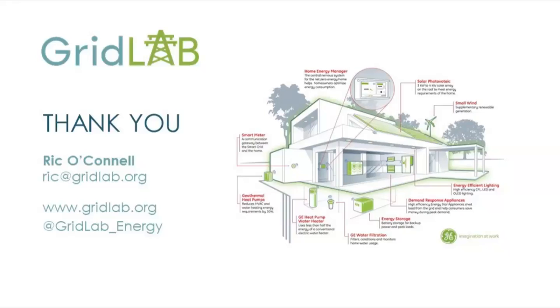And his point about volt watt is also another very good one, which is one of the things that is a positive for volt watt for everybody. If you didn't enable volt watt and the voltage did get out of the ANSI range, eventually these systems might actually just trip offline because the voltage has gone too high. And now your DER is completely offline and may take some time to reconnect. You may absolutely prefer that it sort of ramps down, sort of self-curtails for a few minutes until the voltage issue is resolved and then comes back online, as opposed to completely tripping offline.